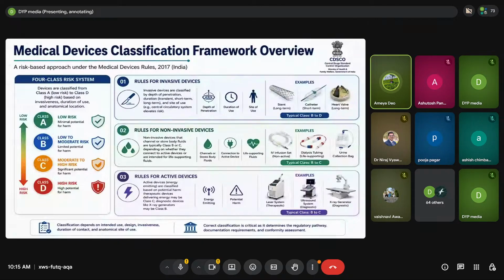The easy way to understand this is, as the patient risk increases, the regulatory requirement also increases. So you require very little documentation for Class A devices, while Class D devices require very stringent documents, even clinical trial documents. Also, the classification depends upon several factors, such as the intended use, the degree of invasiveness, the duration of contact, the anatomical location where the device is used, and also what energy will be delivered by the device.